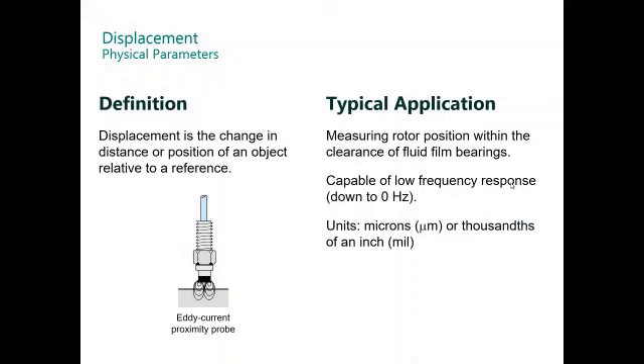Displacement is the change of the distance or position of an object relative to a reference. For displacement, we use the eddy current transducer or proximity probe. The typical application is measuring rotor position within the clearance of fluid film bearings. It is the only sensor capable of measuring zero hertz. Zero hertz is static or position. The units are microns peak-to-peak or thousandths of an inch or mils.